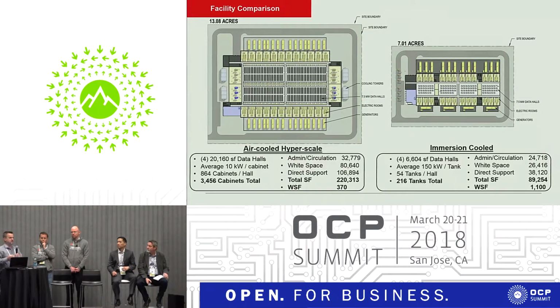Okay, so how do we go and take these tanks and implement them into a facility? So for this comparison, as we discussed before, we have an air-cooled hyperscale, 10 kW per rack. In an attempt to not get too aggressive with the system infrastructure, something that a lot of end users would look at and say, well, I wouldn't even do that in my data center today, we avoided the direct evap and some of those other cooling systems here. Instead, we went with water-cooled chiller plants with water-side economizers, hot aisle, cold aisle containment with chimney-style racks, perimeter CRACs, an architecture that should look fairly familiar to everybody here. We maintained N+1 throughout.